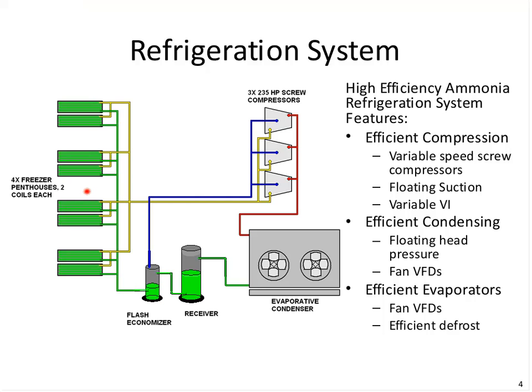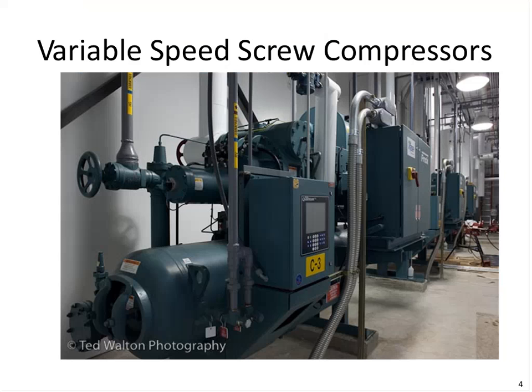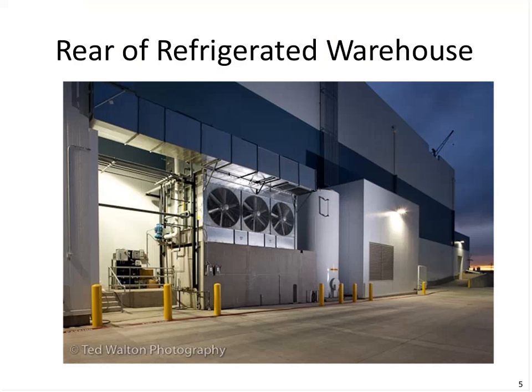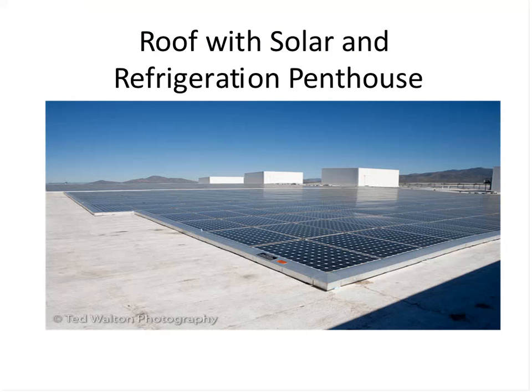Well, I'm going to go back a slide here. Next slide forward. Okay, we'll take a look at those evaporators are in penthouses. Above it here is the variable speed compressor itself, and variable frequency drive inside this panel right here. Compressor. There's also a slide valve. You can see that in that diagram there. Here's the back of the house, the evap condensers, and there is a refrigerant recovery tank here in case there's ever an accidental release of ammonia. Can be placed in that tank.